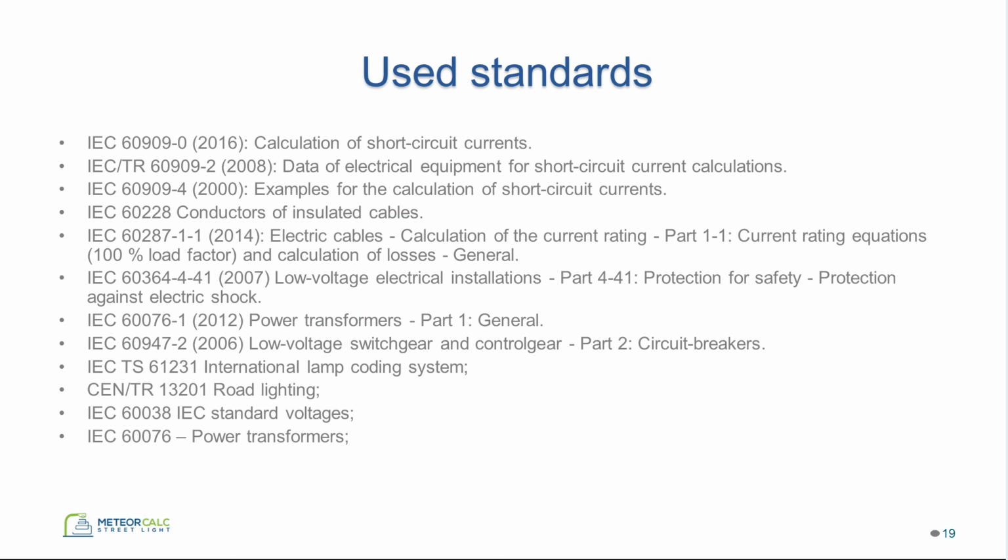Please note that several conditions of the main procedure of short-circuit current calculations described in the IEC 60909 have been changed in 2016. Since version 1.5, MeteorCalc performs electrotechnical calculations based on the latest version of the standard.